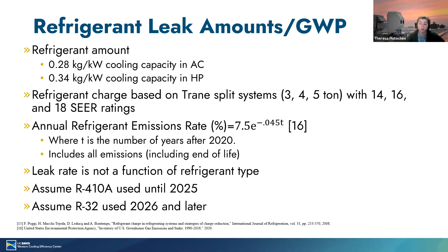Okay, so we use data from the US EPA to estimate the annual refrigerant emissions as a function of initial charge. Refrigerant emissions rates are estimated based on some refrigerant loss at the time of installation, some loss for operation of the system, and then some loss at the end of life at removal. We've taken all that into account and estimated a loss rate of 7.5% per year, which declines based on the date of installation past 2020 because we assume that there will be improved manufacturing, installation, and operation practices with time. As I mentioned, we assume that R410A is used until 2025, and then R32 is used 2026 and later.